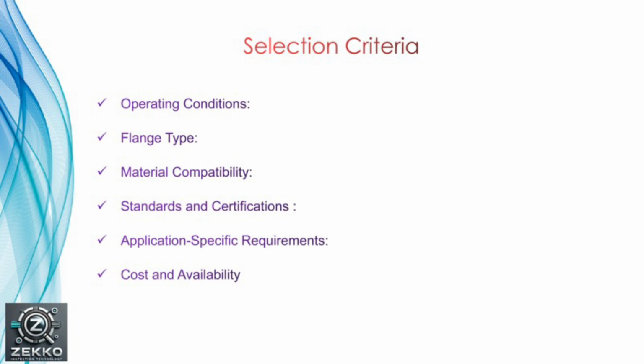It is typically between 125 to 255 micro inch Ra value. The third parameter is material compatibility, like gasket material and filler material. We should choose the filler material based on temperature and chemical compatibility. One filler is graphite for high temperatures and chemical resistance. Another generally used is PTFE for chemical resistance but limited to lower temperatures. A mica filler is also available, but it is not commonly used. The metal winding in this gasket also plays an important role. The choice of metal, stainless steel, Inconel, Monel, depends on the chemical exposure and the corrosion resistance required.